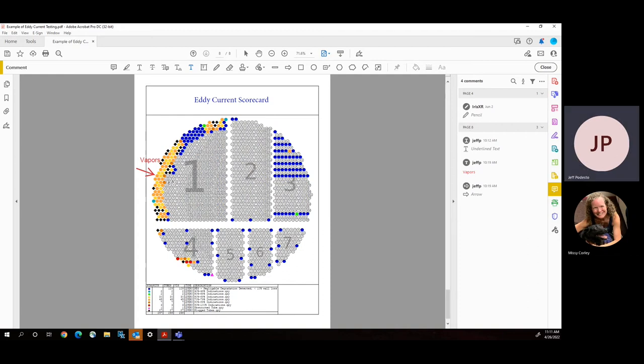Along with the customer, we did an engineering evaluation of what the losses would be if we were to plug a certain percentage of the tubes. And based on our analysis, we were able to determine that they would see fairly negligible reductions in capacity, if any at all.